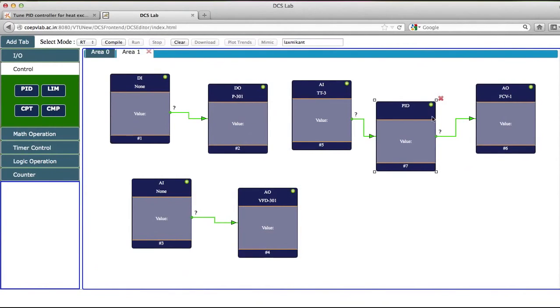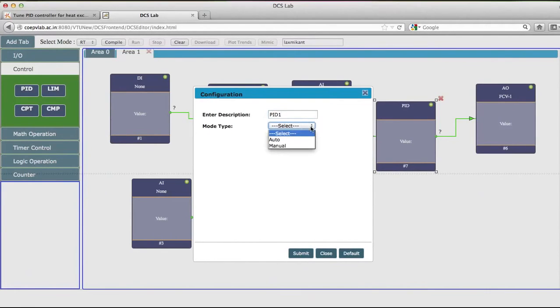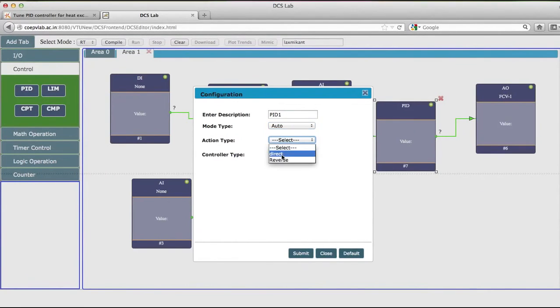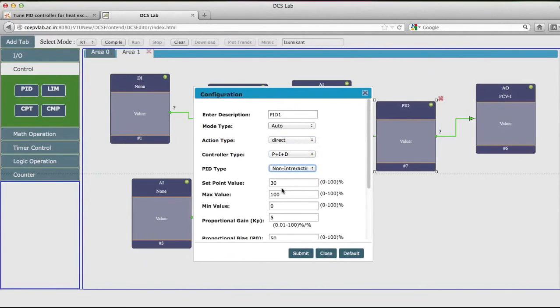Then we will configure the PID controller. Now this PID controller I will write here as PID1 as the description. Then I will select the mode of this PID controller. I wish to put this in auto mode. Action is direct, and the controller type is PID controller.